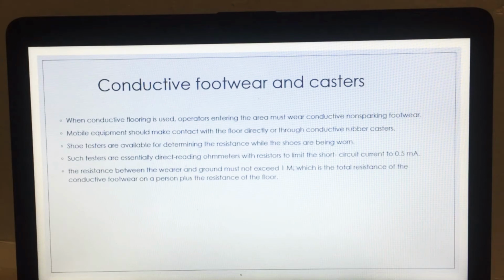Shoe testers are available for determining the resistance while the shoes are being worn. Such testers are essentially direct reading ohmmeters with a resistor to limit the short circuit current to 0.5 mA. The resistance between the wearer and ground must not exceed 1 megaohm, which is the total resistance of the conductive footwear on a person plus the resistance of the floor.